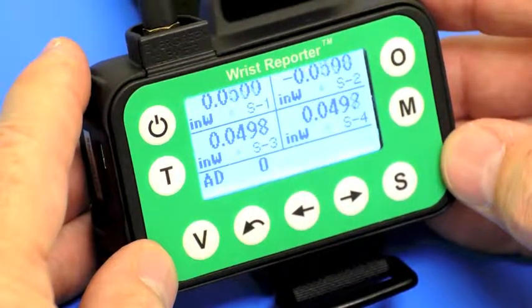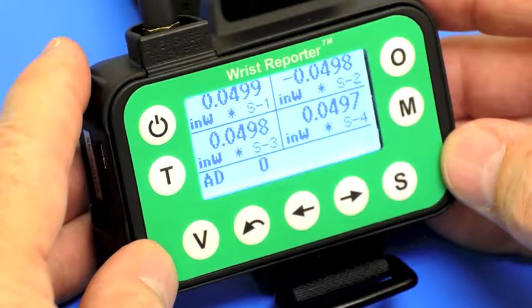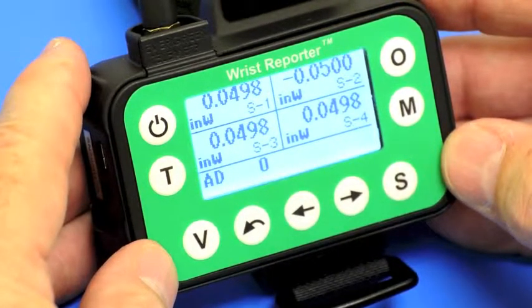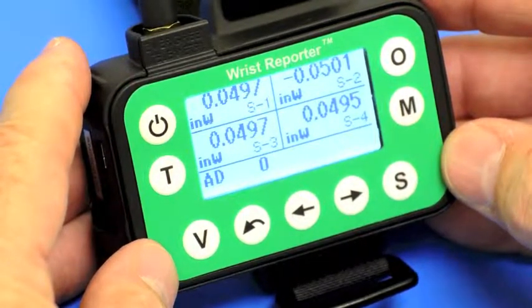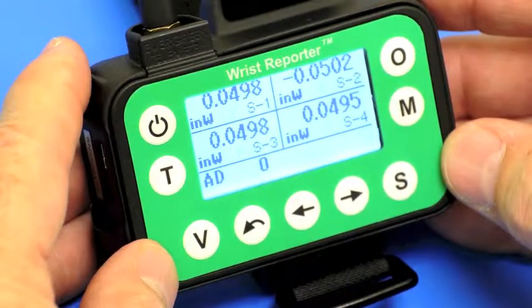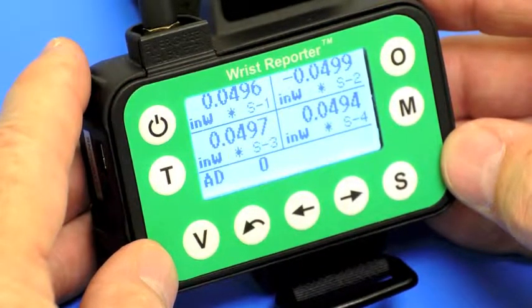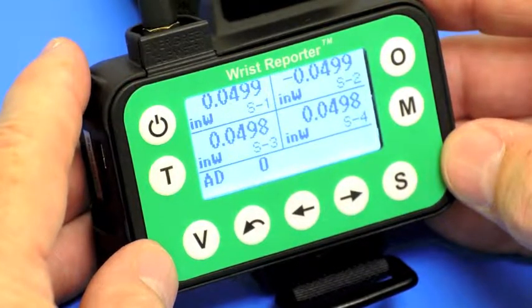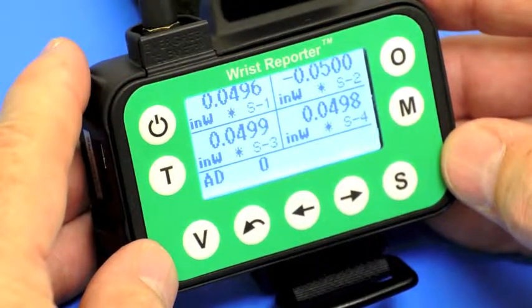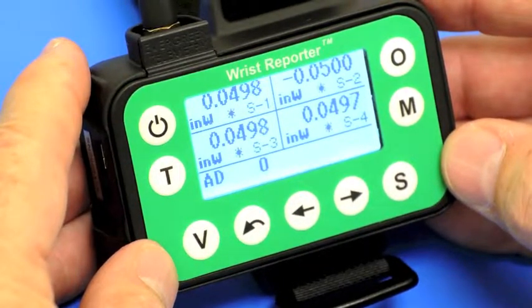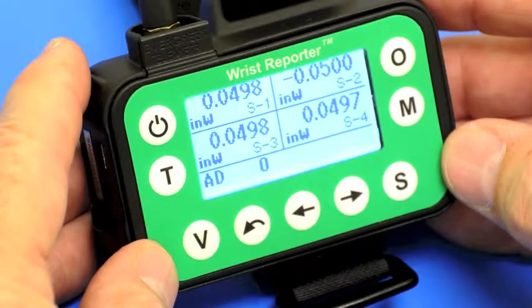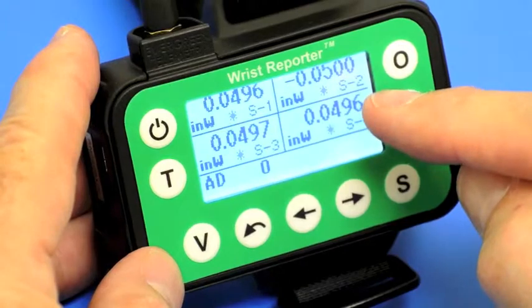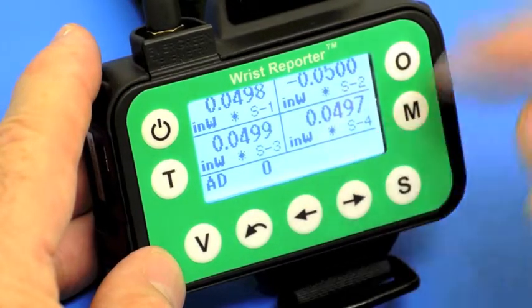I'd like to demonstrate the memory operations of the Wrist Reporter. The setup is one we showed previously, where we have four different pressure modules being used in conjunction with the central pressure calibrator. So 0.05 inches of water column is being forced upon four different sensors: sensor 1, sensor 2, sensor 3, and sensor 4.